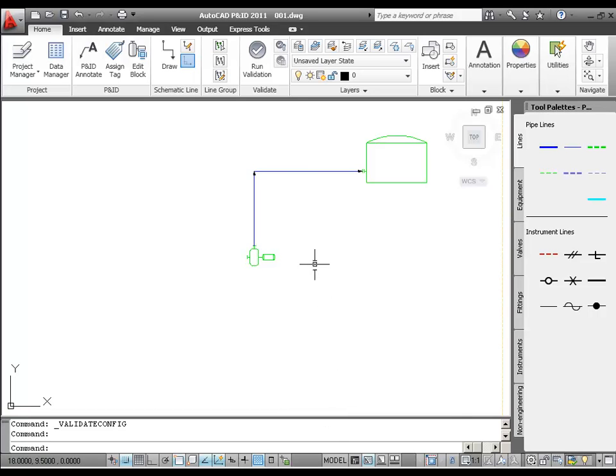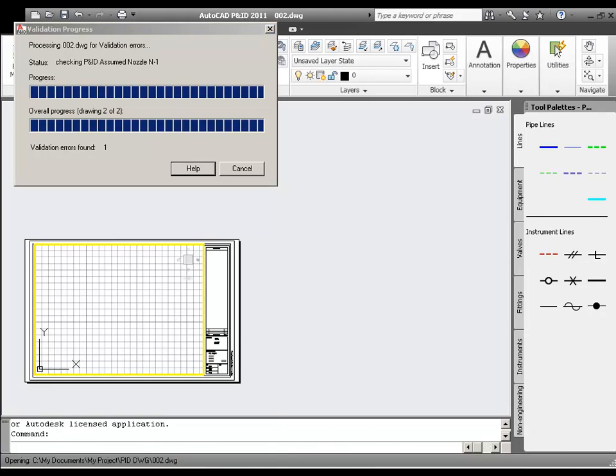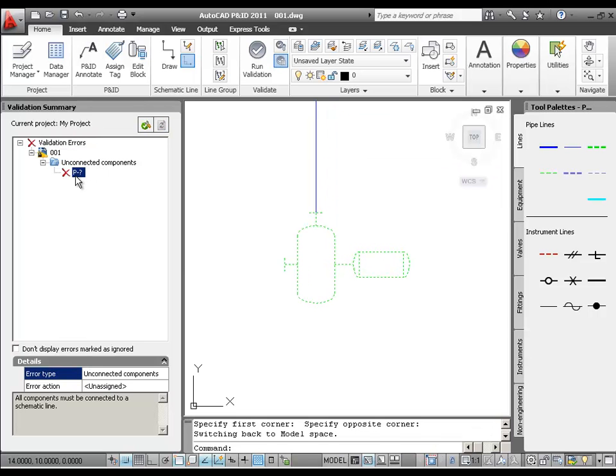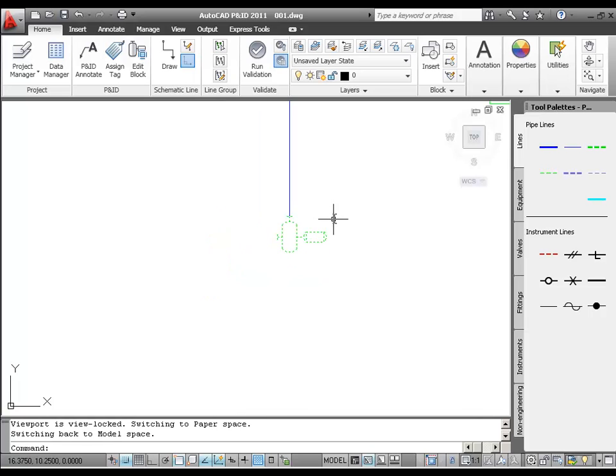Now we'll validate this drawing. Back in the ribbon, we'll click Run Validation. We get a Validation Progress dialog box. When the validation is complete, the Validation Summary window displays the results. We have an unconnected component error. I'll click the Error node. In the drawing, the horizontal centrifugal pump is highlighted because its left nozzle is not connected to a line. This is fine — we just haven't gotten to this other side of the pump yet. We'll go ahead and fix that now.